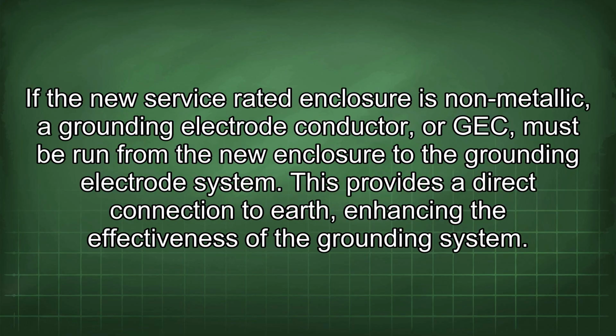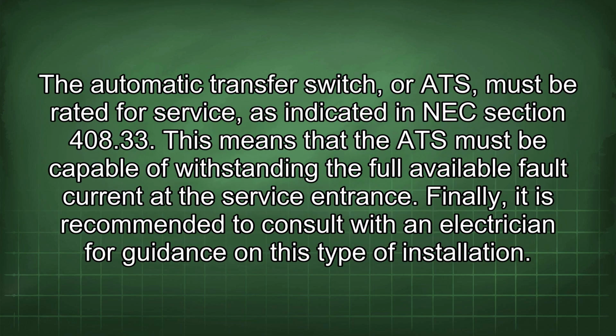If the new service-rated enclosure is non-metallic, a grounding electrode conductor, or GEC, must be run from the new enclosure to the grounding electrode system. This provides a direct connection to earth, enhancing the effectiveness of the grounding system. The automatic transfer switch, or ATS, must be rated for service, as indicated in NEC Section 408.33. This means that the ATS must be capable of withstanding the full available fault current at the service entrance.